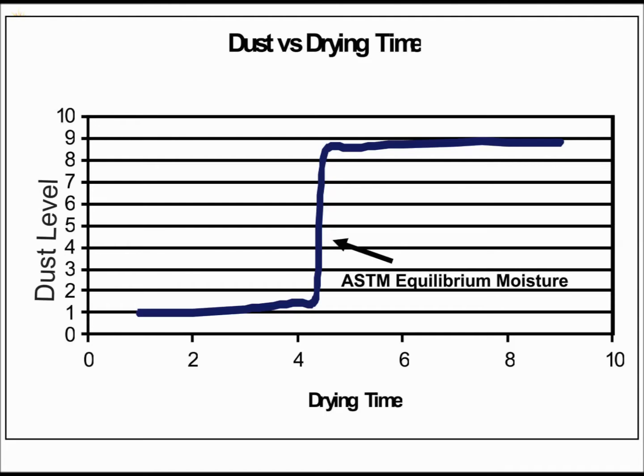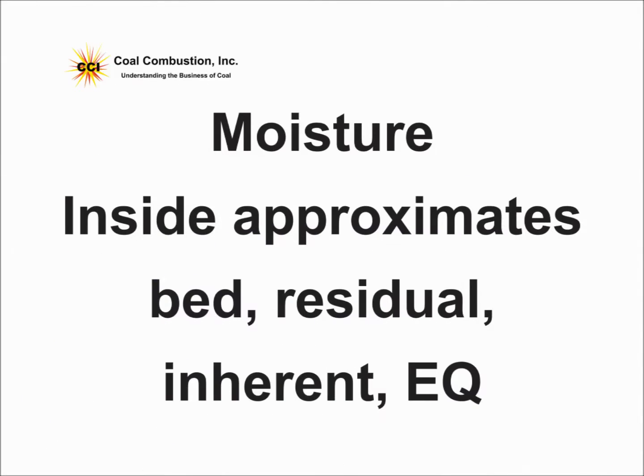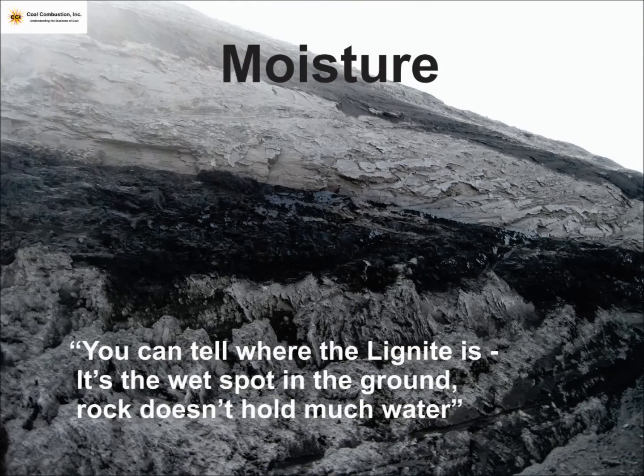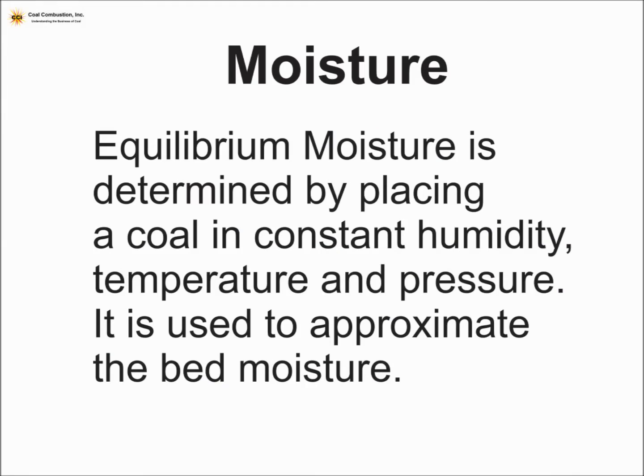This equilibrium or bed type moisture — sometimes called the residual moisture in the actual ASTM test — is that moisture that the coal has even when it's underground. Before it's mined and broken up into chunks and exposed to the environment, that's the moisture we're trying to get at. One lignite mine told me you can tell where the lignite is because that's where the wet spot is in the ground — the rock doesn't hold much moisture. Equilibrium moisture is a test where we look at the moisture a coal will hold at a constant humidity, temperature, and pressure, and this approximates that bed moisture.